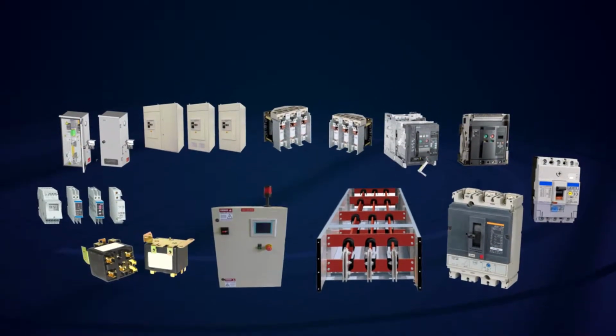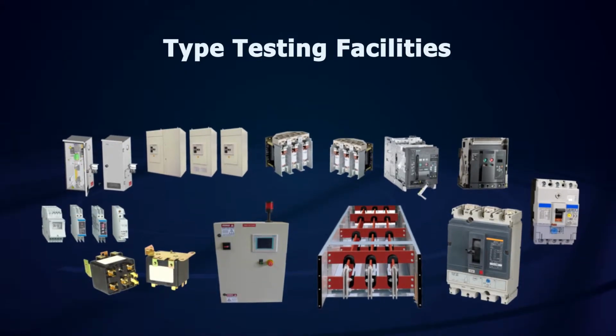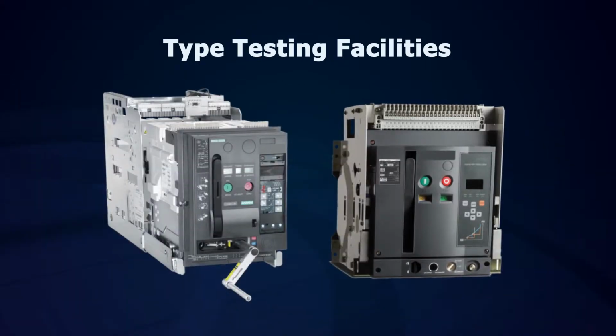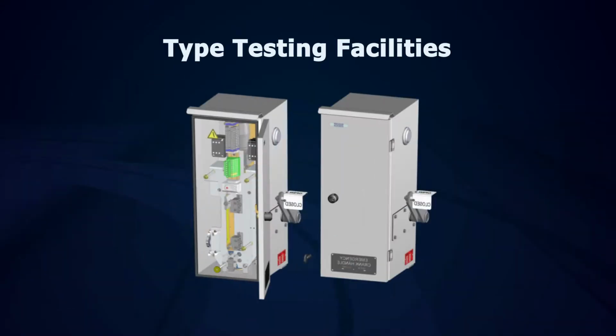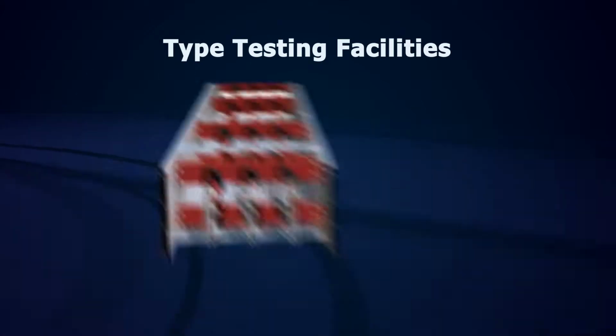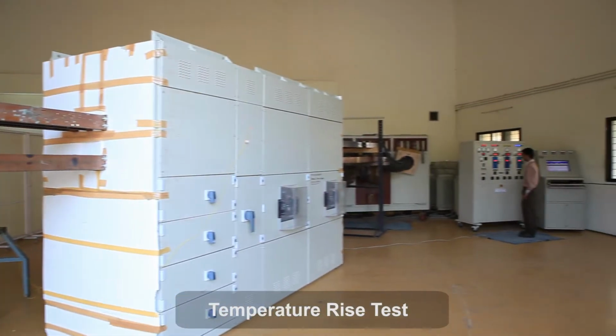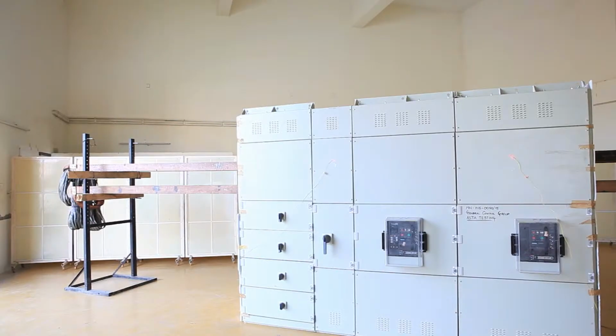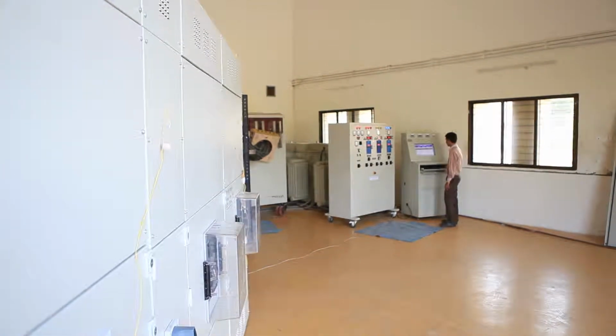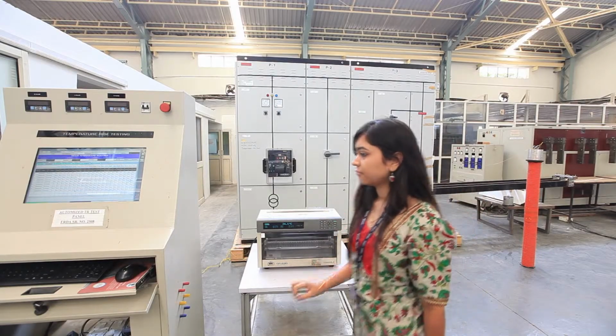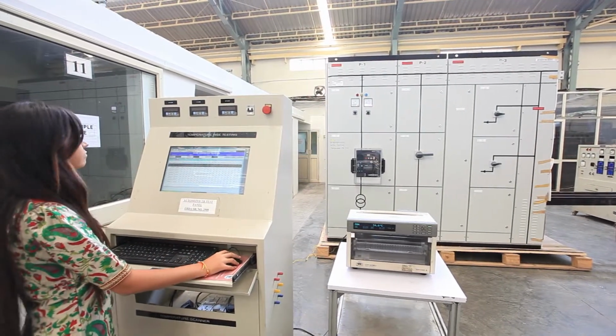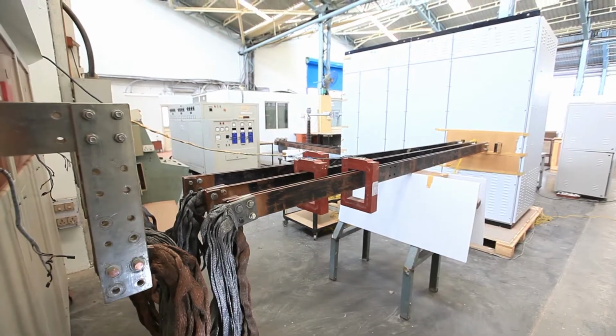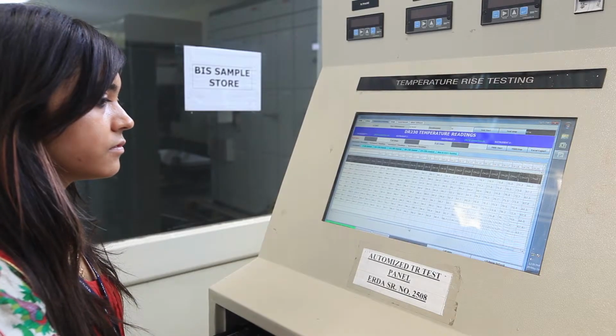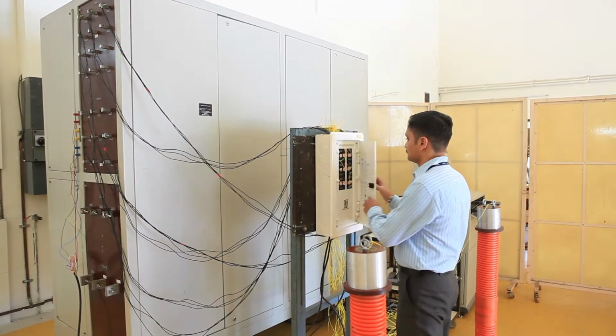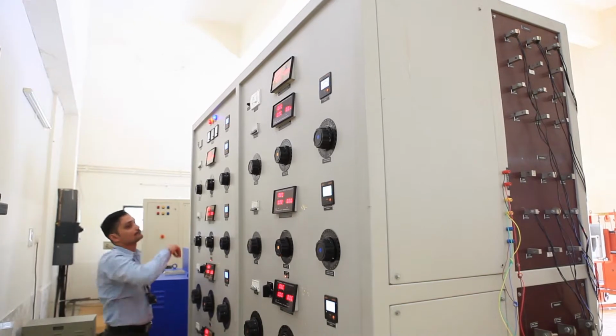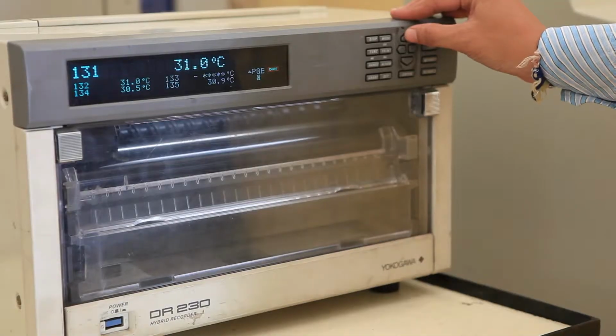ERDA's switchgear laboratories have complete type testing facilities for low voltage products like MCCBs, ACBs, contactors, starters, control switches, relays, panels, and bus ducts. 5 temperature rise tests can be conducted simultaneously. The facilities include 1 current source of 20 kiloamperes, 2 sources of 10 kiloamperes, and 2 sources of 5 kiloamperes test beds. These facilities are fully automated with temperature recording capabilities.